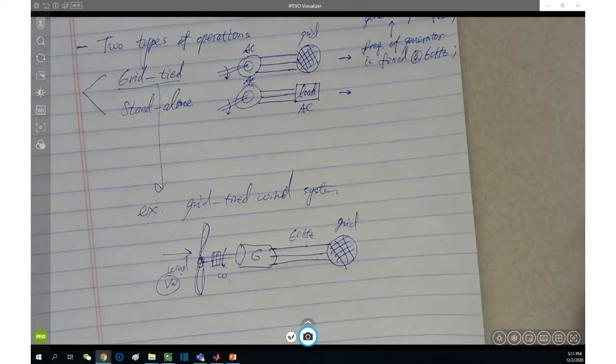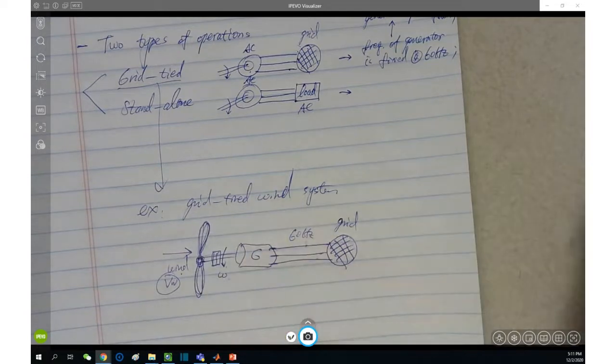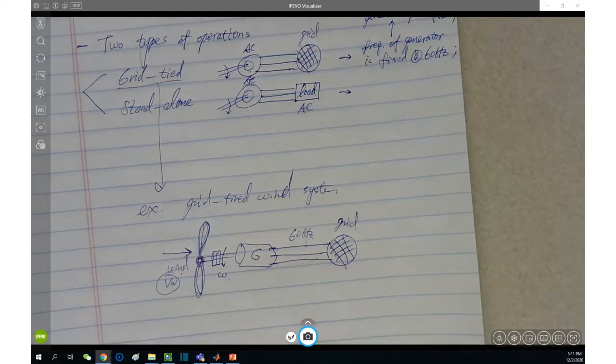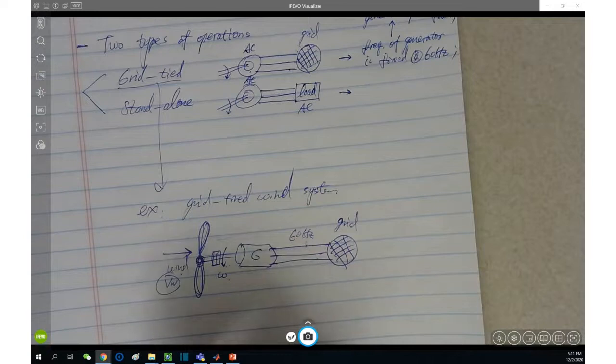A second thing you're talking about is actually giving a load. Is that what you say? Yeah, if they need to maintain the generator at the 60 hertz speed and there's no wind out today, so the wind turbine's not spinning. Well, if there's no wind or wind speed is too low, below the so-called cut-in speed, what you need to do is either shut off this generator. You have a brake or shut-off system to do that. Or you have to let it run. So the generator is not a generator anymore, right? But a what? A motor. Yes, you are consuming energy rather than generating energy. That's true. So generally speaking, below the cut-in wind speed, people won't turn on the system. There's a cut-in wind speed there to decide turn on or off of the system.